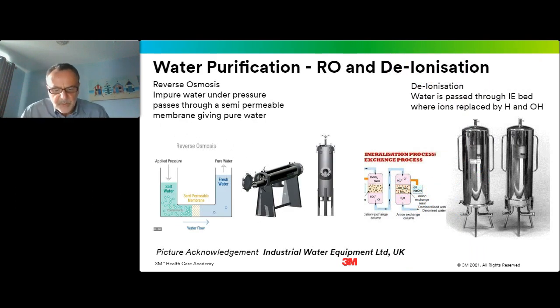So in the hospital environment, water purification is very important. And two typical technologies which would be used would include reverse osmosis and deionization. In reverse osmosis, impure water is pressurized and that forces it through a semipermeable membrane, which is essentially acting like a filter at the molecular level. This water will pass through the semipermeable membrane, but the salts and materials dissolved in it will not pass through. So you end up at the exit end of this technology with fresh water, which is purified and can then be used in further processes.